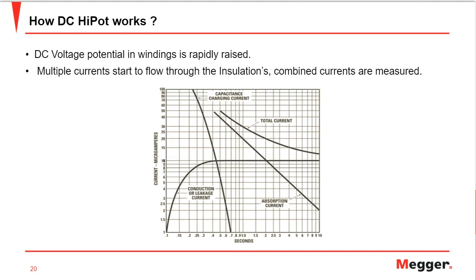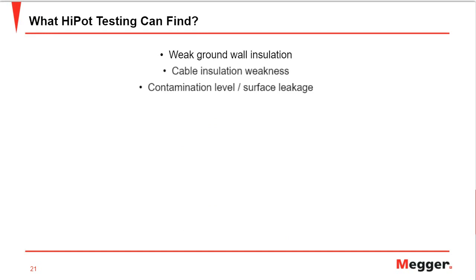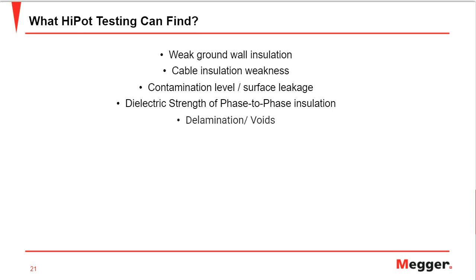We'll see what a DC high-pot test can help us find. First of all, weak ground wall insulation, cable insulation weakness, and of course the contamination level and surface leakages. The dielectric strength of the phase-to-phase insulation can also help us find delamination or voids.